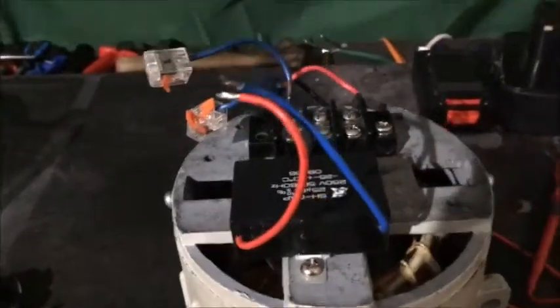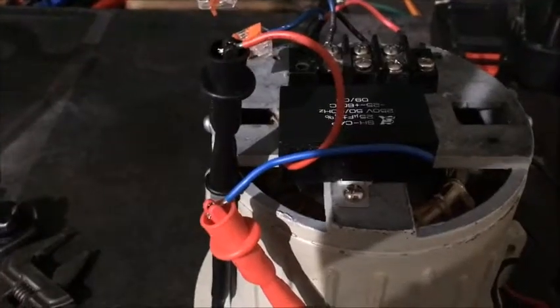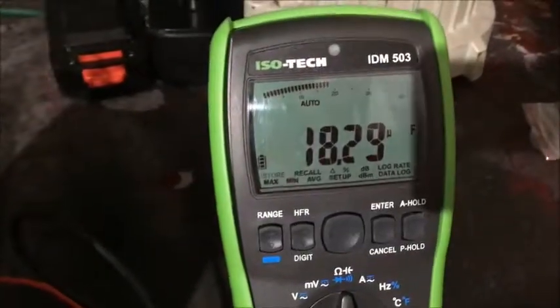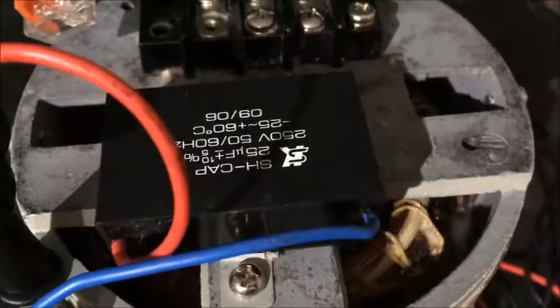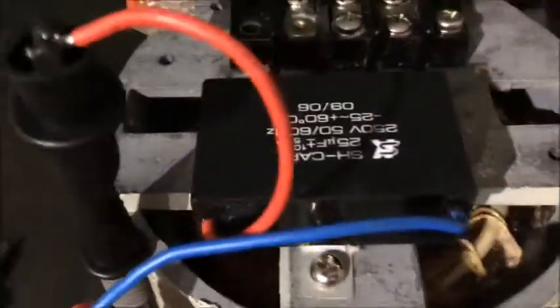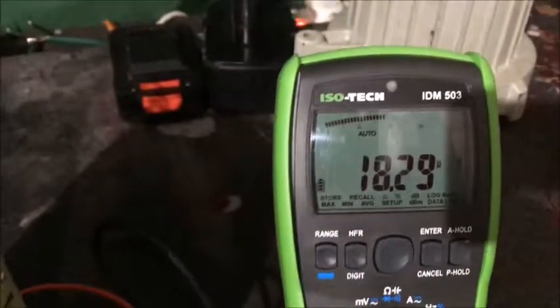Those are the two wires of the capacitor. I'm going to test between them with a multimeter - leads connected, switch it on. Reading 18.2 µF. It's a 25 µF capacitor, so 10% tolerance brings it down to 22, so it's pretty much wearing out, but it's not the cause of the fault.